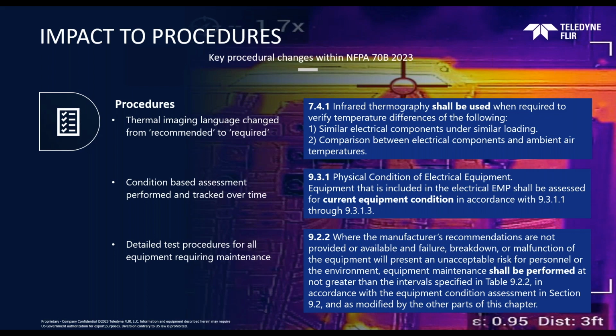And then detailed test procedures for all equipment requiring maintenance. Many organizations and standards will reference manufacturer recommendations, but within NFPA guidance, when those recommendations are not provided or available, and if the failure, breakdown, or malfunction of equipment presents an unacceptable risk for personnel or environment, they provide a very detailed list of activities and intervals within table 9.2.2 based on the condition of that asset.